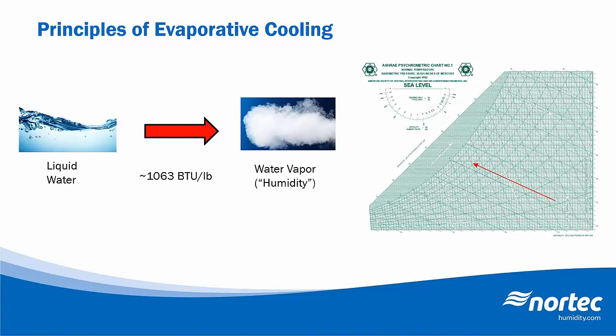So before we go any further, let's take a quick look at the basics of evaporative cooling to see why this type of technology is a great way to reduce energy consumption in a data center. So evaporative cooling technologies have been around for a very, very long time, and even your body uses it as a means to cool down by sweating when you're overheated. Now, thermodynamically, the energy required to drive the phase change from liquid water to vapor is the same regardless of how you do it. So it takes about 1,063 BTUs of energy to evaporate 1 pound of water.